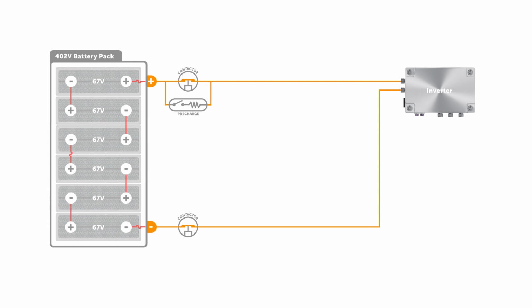Next, between just one of the contactors in the battery, we'll find a current sensor. This is the main feedback the BMS has in order to determine how much charge is entering and leaving the battery. And this sensor is used to determine the state of charge, calculate the power, and ensure that the battery is operating within its required limits. The battery pack may also contain a set of contactors for DC fast charging.